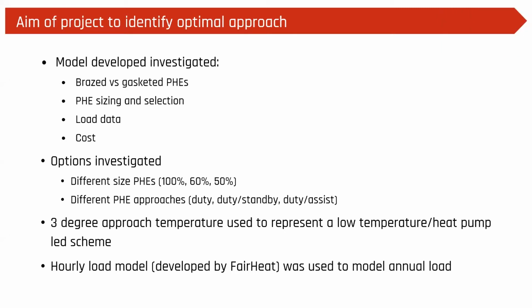Some of those options we looked at included different size plate heat exchangers, so going at one size at 100% and smaller plates. Also looking at different plate heat exchanger arrangements, so duty standby or duty assist as well. The model used a 3-degree approach temperature across the plate heat exchanger. This was used to represent a low temperature scheme or heat pump led scheme. I also used load data from a theoretical hourly load model, which was developed by FairHeat. This load model had 4 different scheme sizes, going from 100 units to 1,000 units. So scheme size was also investigated within this, but for the purposes of this presentation, I'm just going to look at the 250 unit size scheme.